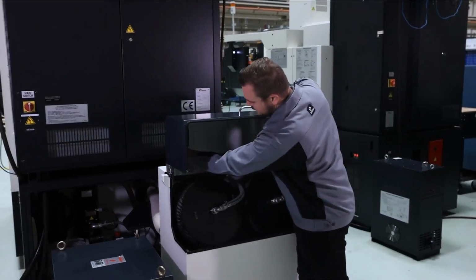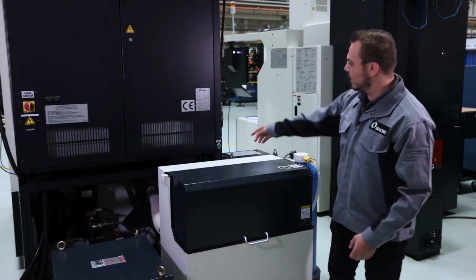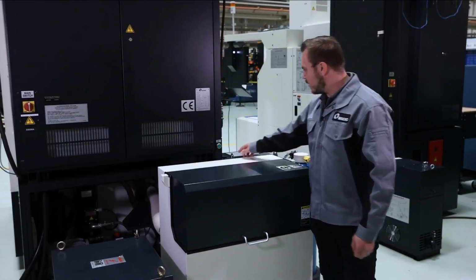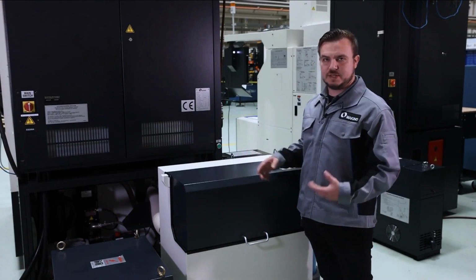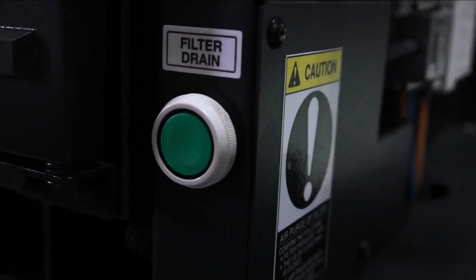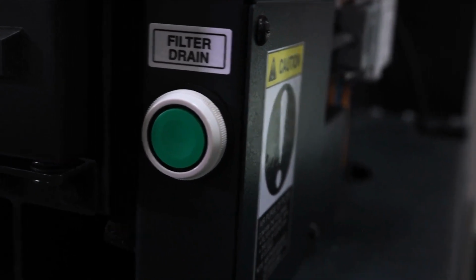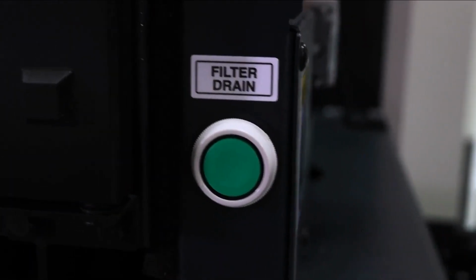I'm going to close this hood, and right here on the back of the machine we have a filter drain button. What this does is when the pump is turned off, this will force air through the filters and get all that water out, so when we're pulling those filters out, we don't have water going all over the floor.